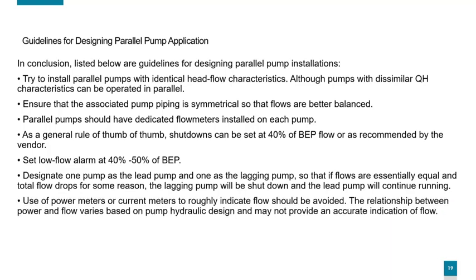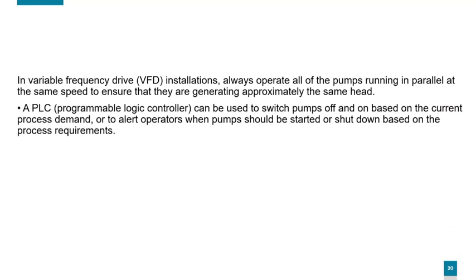Use of power meters or current meters to roughly indicate flow should be avoided. The relationship between power and flow varies based on pump hydraulic design and may not provide an accurate indication of flow. For variable frequency drive VFD installations, always operate all the pumps running in parallel at the same speed to ensure that they are generating approximately the same head. A PLC, programmable logic controller, can be used to switch pumps off or on based on the current process demand, or to alert operators when pumps should be started or shut down based on the process requirements.